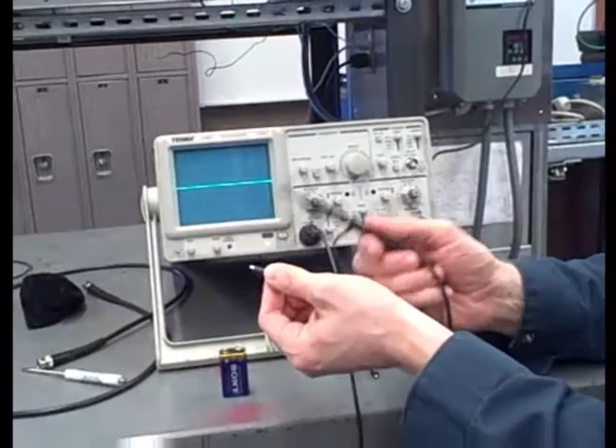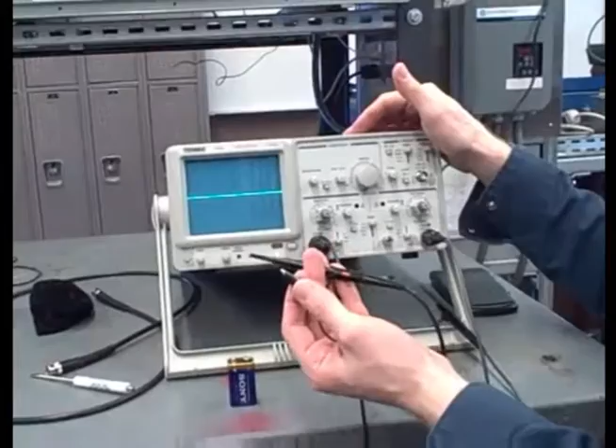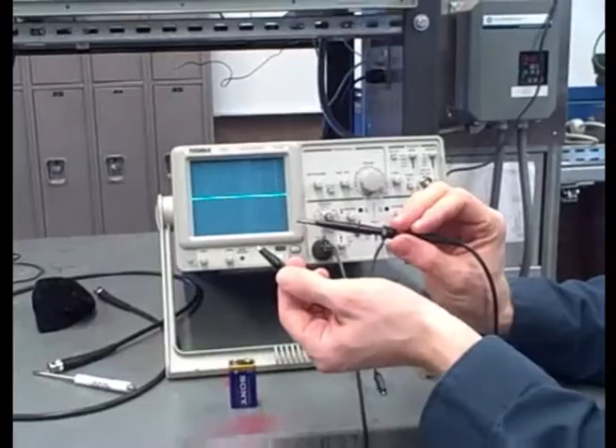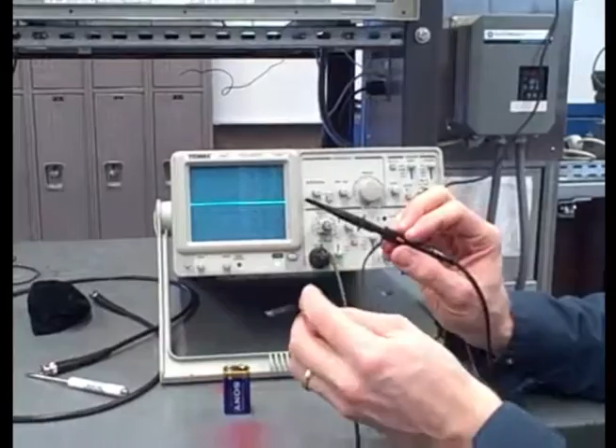Because this lead right here, even though you may think of it as being the black colored lead on a voltmeter, just like this is a red colored lead, this black colored lead actually goes to earth ground whether you like it or not. So every time you make a connection to a circuit like this, you are grounding one part of that circuit, whether you like it or not. You better be prepared for the results. So you cannot be doing phase-to-phase measurements on an AC system, otherwise this thing would be a direct ground fault. And like I said, if you're holding it, it's going to be very, very nasty.